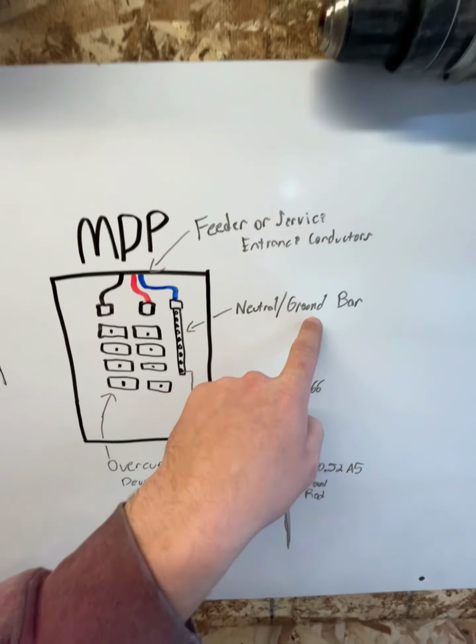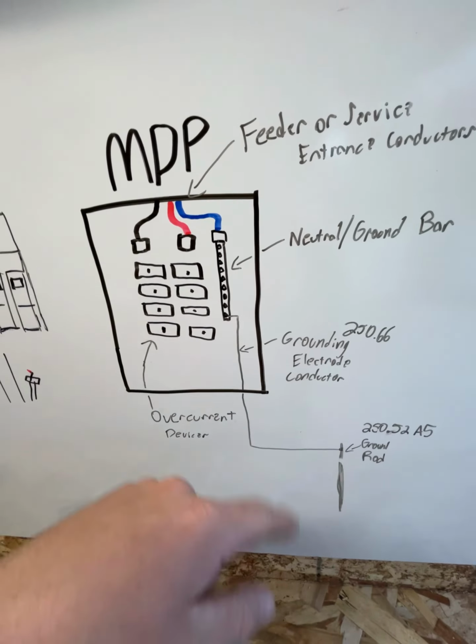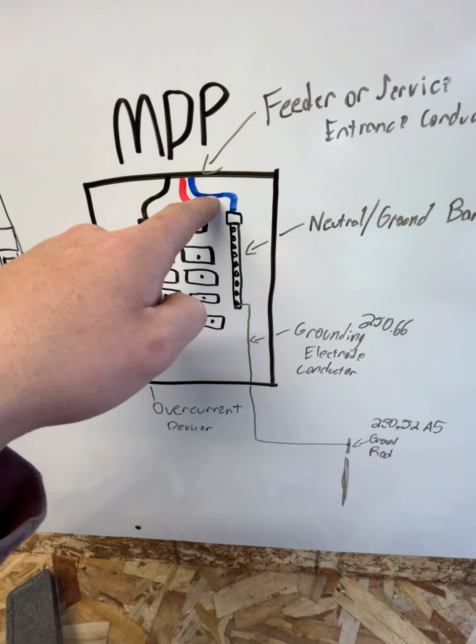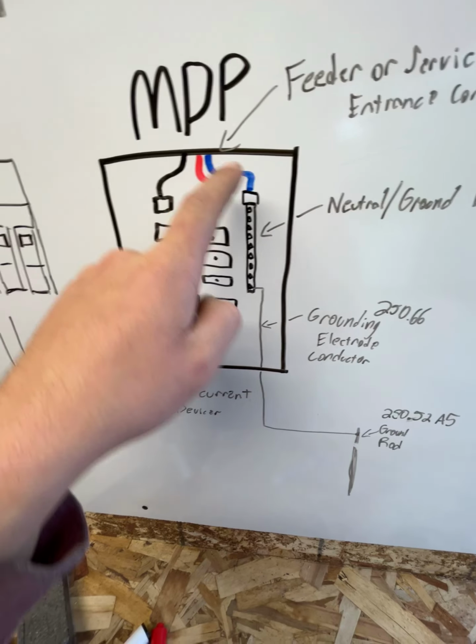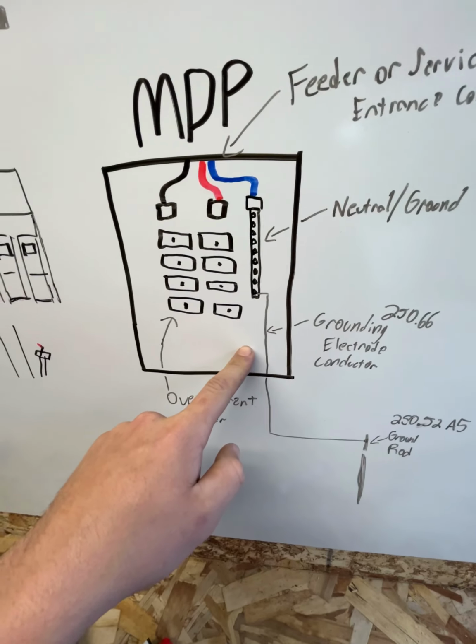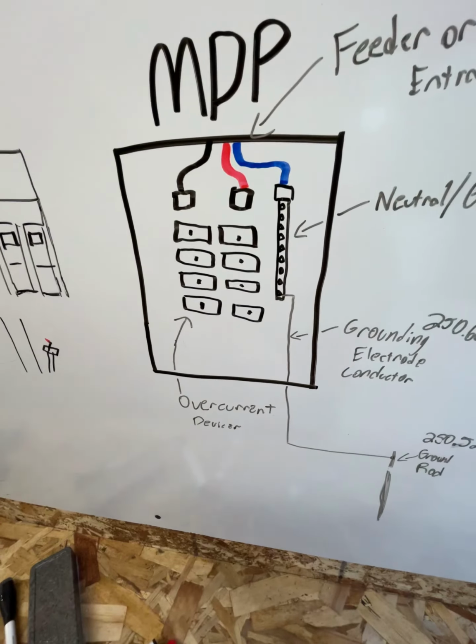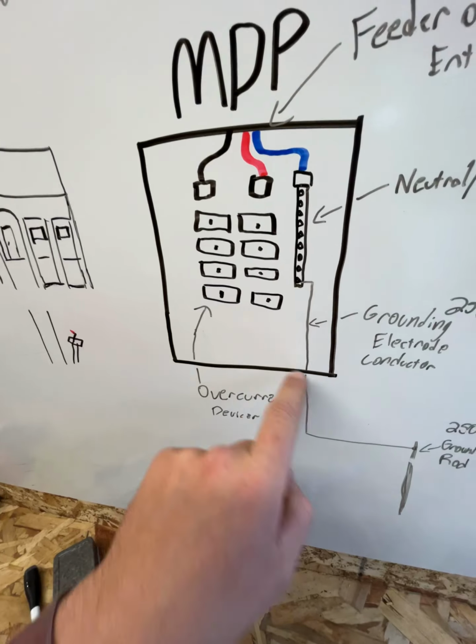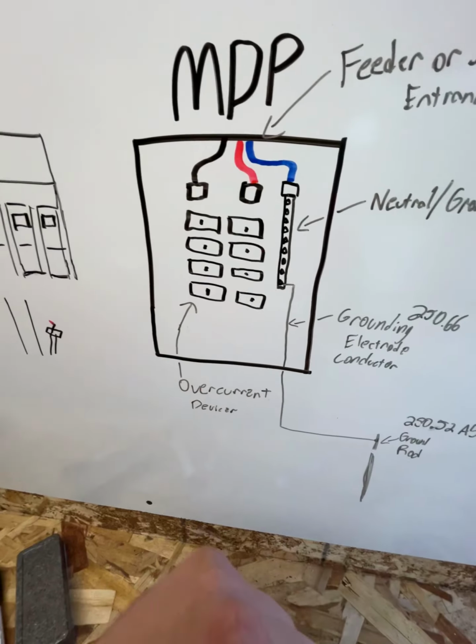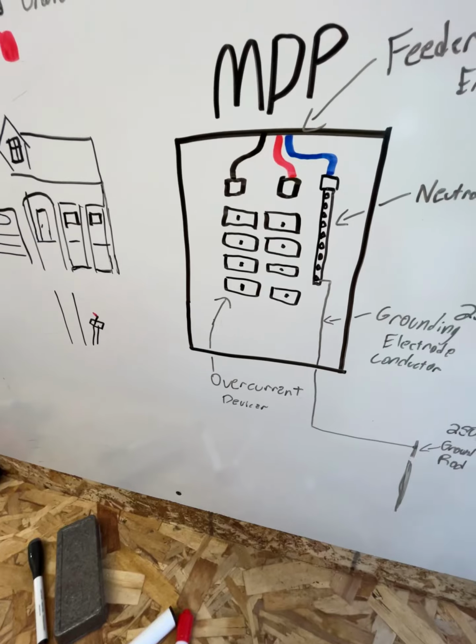Then I have my neutral and ground bar — only in the MDP will we bond our neutral, our blue wire in this instance, to our ground wire, right? Only in this main panel. So if there's a sub panel, we don't bond them again, we just separate them. The enclosure gets bonded as well, and all these other things.